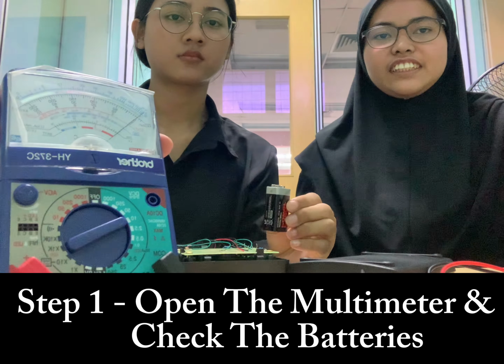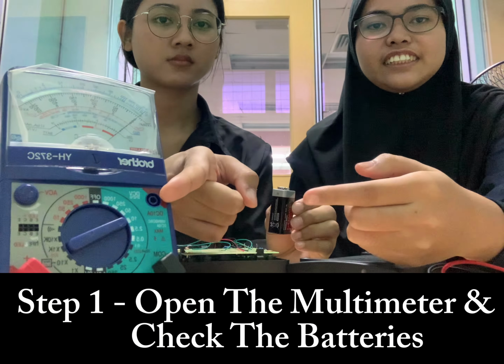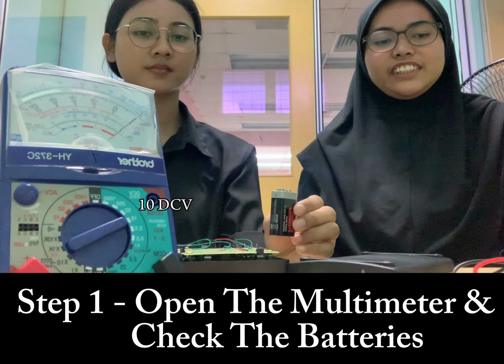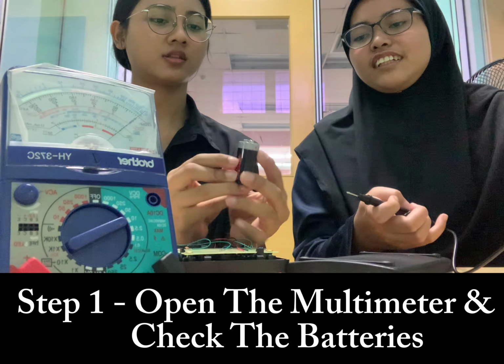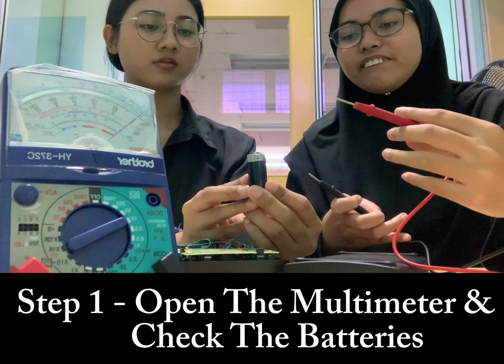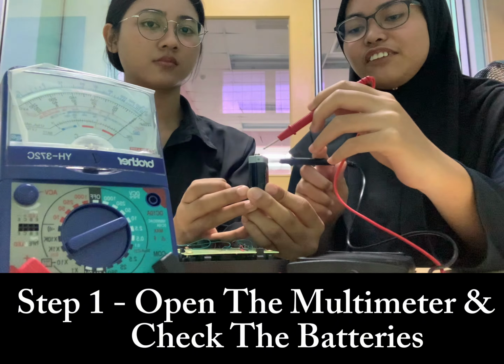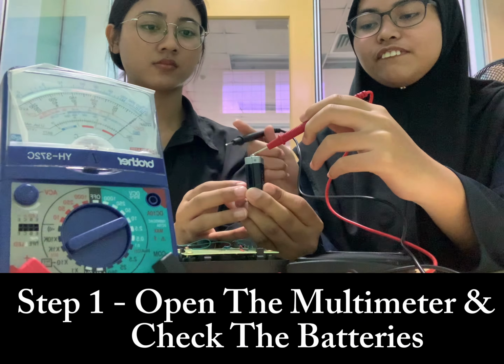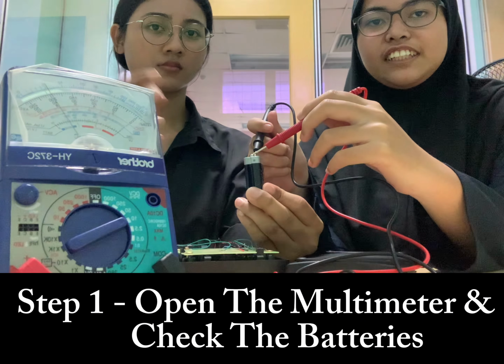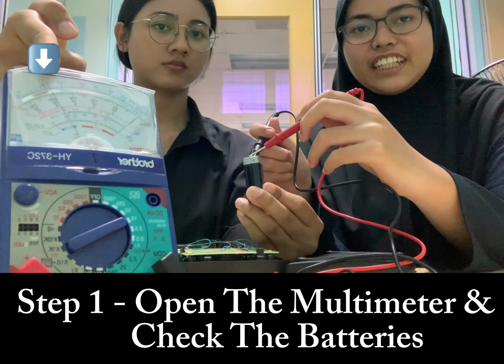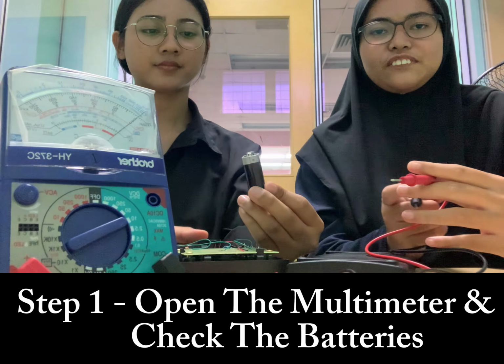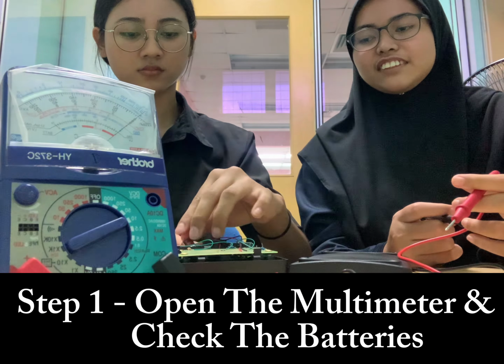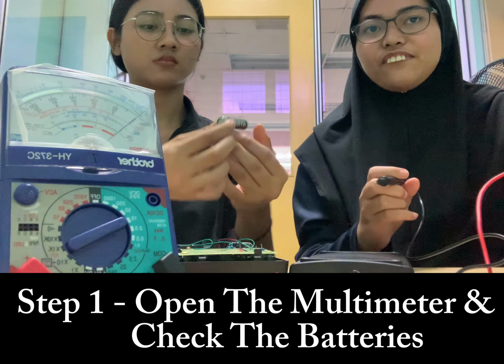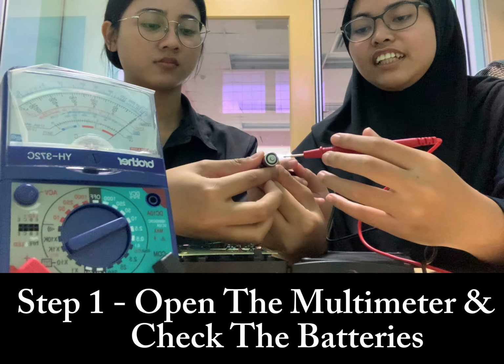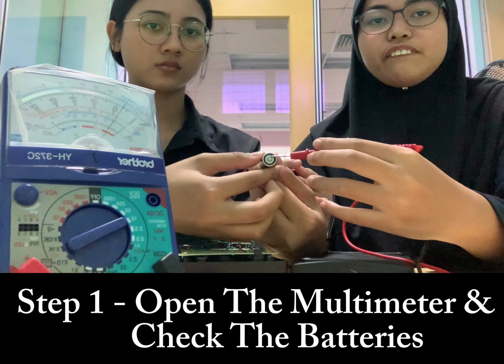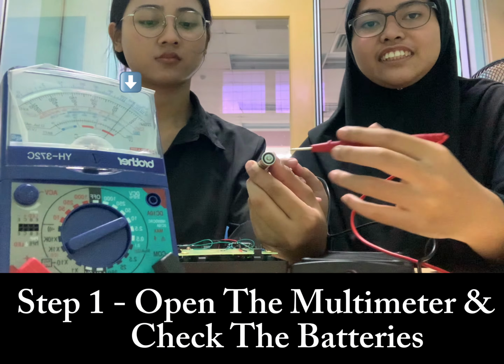To measure the battery, we switch the selector to 10 DCV. Then, the red probe must be on the positive side of the battery and the black probe must be on the negative side. If the multimeter reflects a reading, that means the battery is good to use. Why do we have to check the battery? Because the battery is a common cause of malfunction.